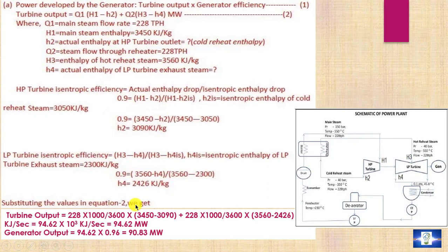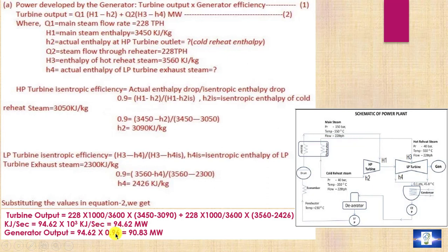Substituting the values, the turbine output equals: main steam flow 228 ton/hr (converted to kg/s as × 1000/3600) × (H1 − H2) = (3450 − 3090), plus 228 × 1000/3600 × (H3 − H4) = (3560 − 2426), giving a turbine output of 94.62 MW. Therefore, the generator output equals 94.62 × 0.96 = 90.83 MW.